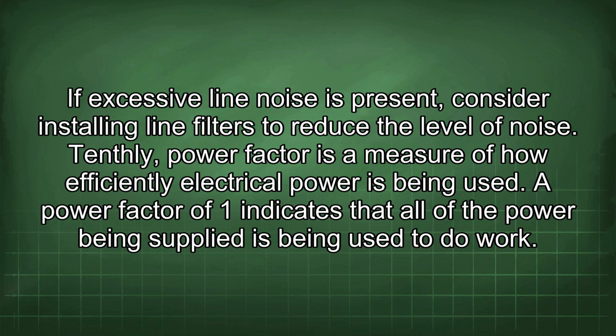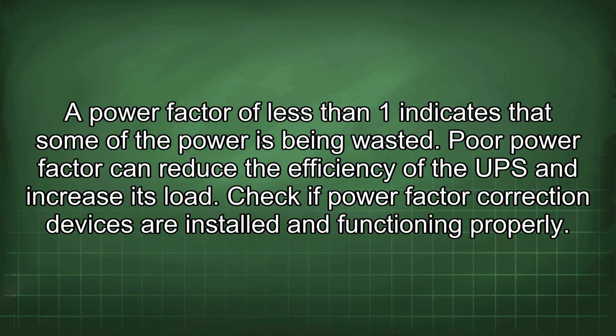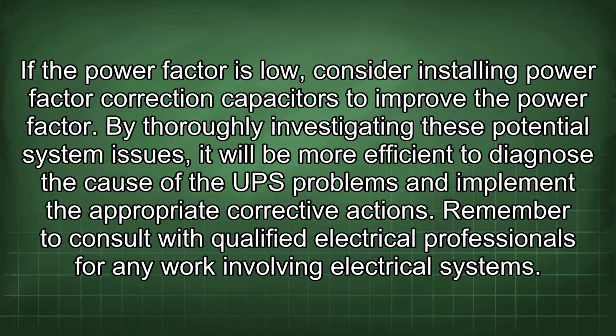Tenthly, power factor is a measure of how efficiently the electrical power is being used. A power factor of 1 indicates that all of the power being supplied is being used to do work. A power factor of less than 1 indicates that some of the power is being wasted. Poor power factor can reduce the efficiency of the UPS and increase its load. Check if power factor correction devices are installed and functioning properly. If the power factor is low, consider installing power factor correction capacitors to improve the power factor.